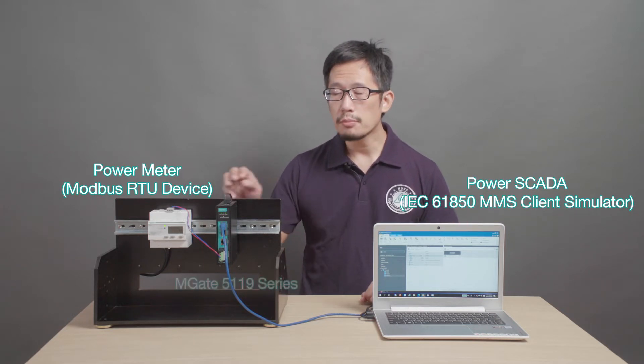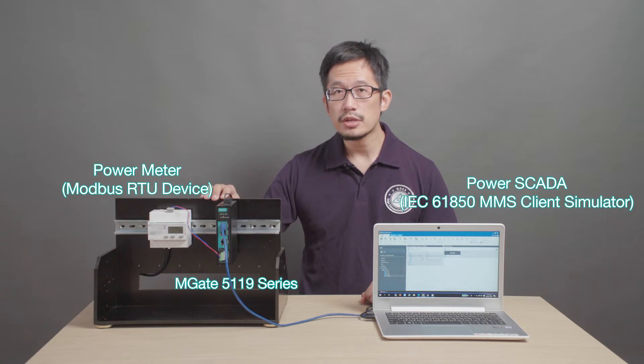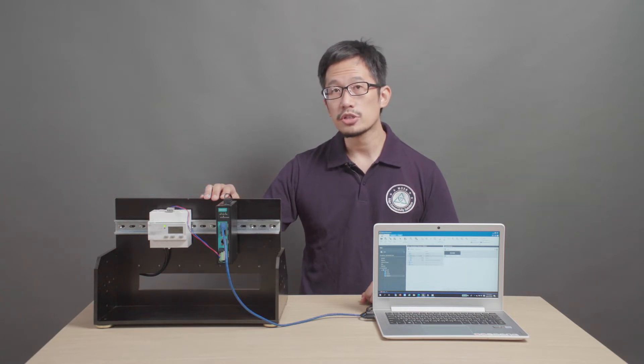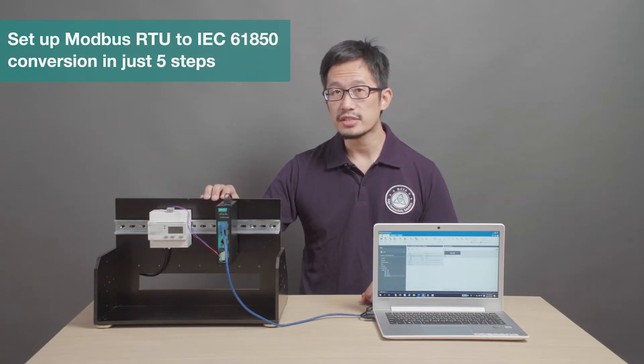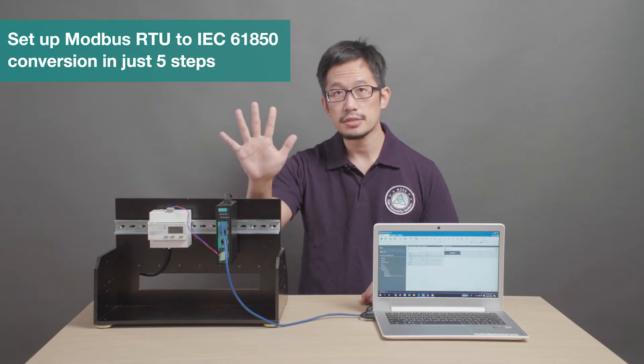we need to convert Modbus RTU protocol, which this power meter uses, to IEC 61850 protocol, which our power SCADA uses. So, we're going to put our MGate 5119 series gateway in between them to handle the protocol conversion for us. And I'm going to show you how you can set this up in just 5 steps.